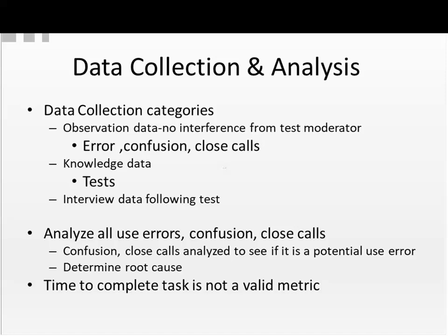Now, it's an important point that the time to complete a task is not a valid metric. You cannot have a criterion where if the person completes the use of the device within X minutes, that's a success. That is not a valid metric.